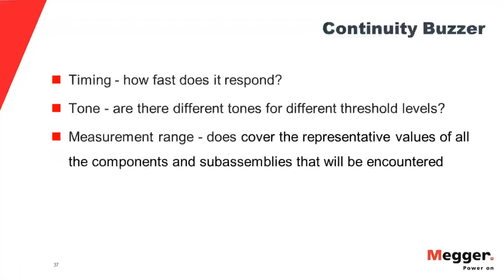Continuity buzzers, these are a good way of getting in and out of continuity testing quickly by not having to look at the numbers. You can set a buzzer and hear the okay, the buzzer goes off. You made the continuity level and you're good, and you can move on. But a lot of times these things are automatically set, and again, a relatively inexpensive tester may only have one continuity buzzer level set, and it may not be realistic for the type of equipment that you are going to work against. So you can look for testers that have multiple continuity buzzer functions, and that the values that you can set are practical against the equipment that you're going to be working on.